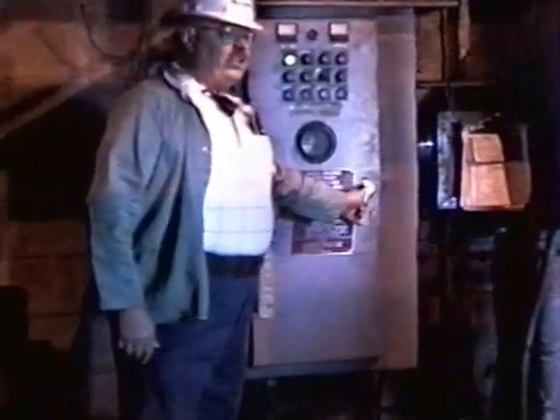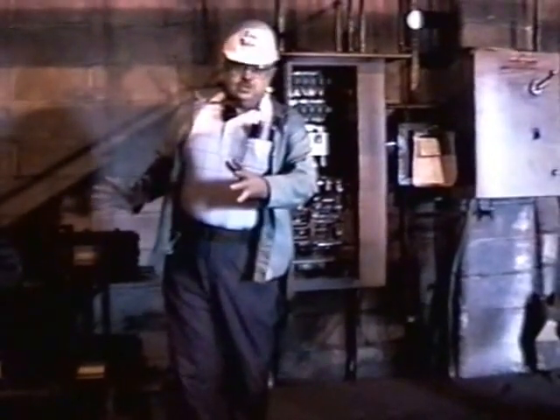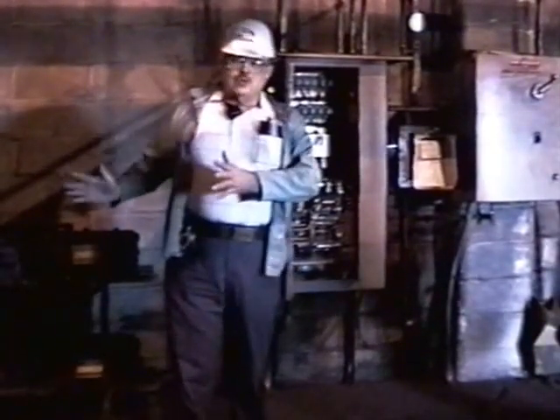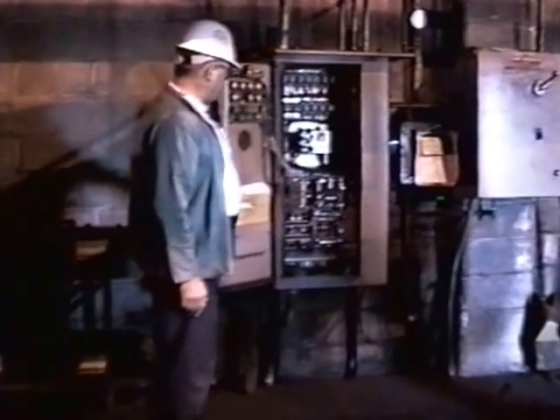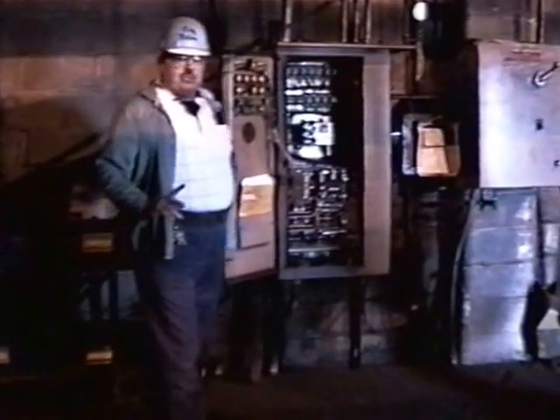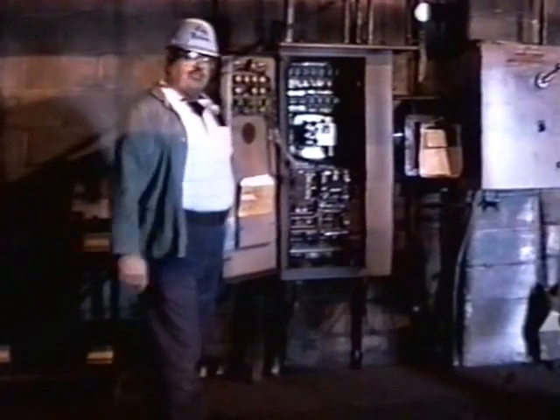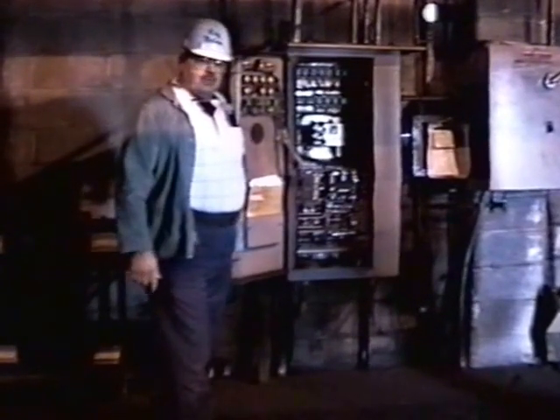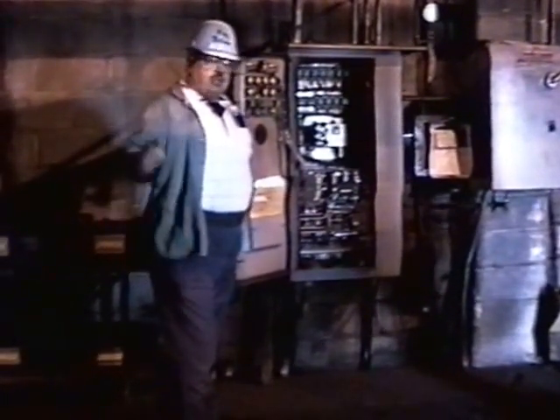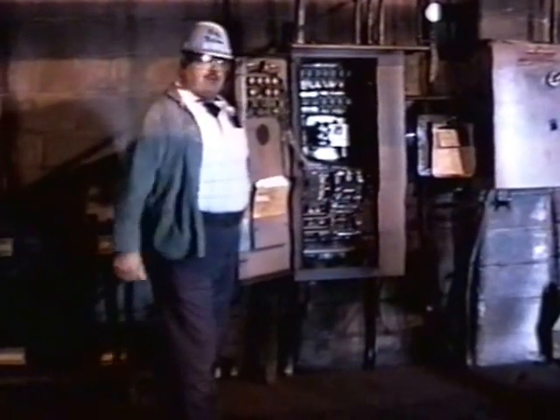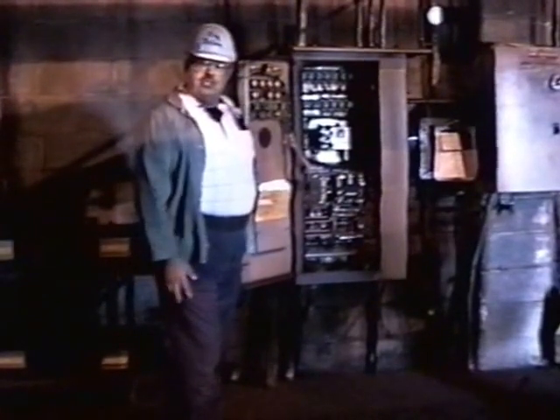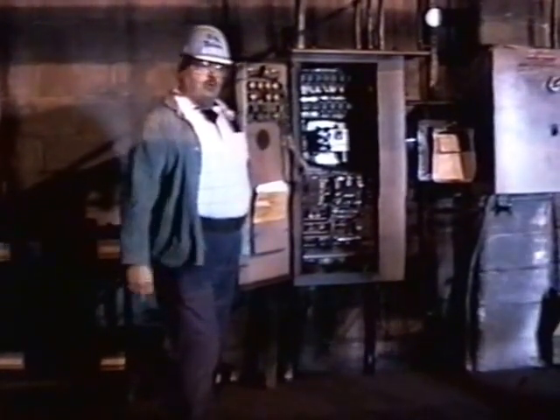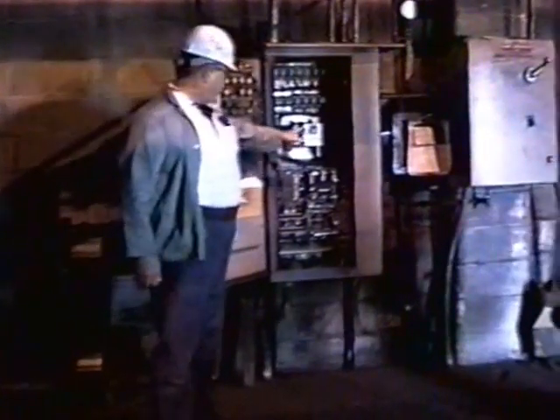The controller is an automatic operation and turns the fire pump on by loss of water pressure. Something happens opening one of the valves, which in turn flows water, the pressure in the mains drops, and the diesel pump turns on automatically. When that happens, someone should respond to this diesel fire pump to make sure that it's operating properly. All the time that this pump operates, someone should be in this building to operate and maintain the cooling system on the diesel pump and to make sure that the water is flowing as needed. There are switches in here, and this switch will stop the diesel fire pump.